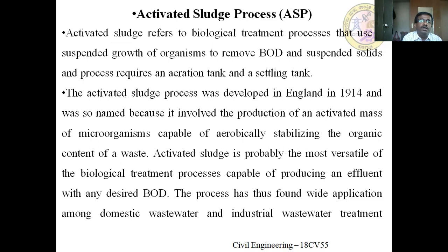Aeration tanks are helpful for mixing the microorganisms with the organic matter and maintaining the system in suspension. For that, in the aeration tank we supply oxygen naturally or artificially. The settling tank is usually termed the secondary clarifier or secondary settling tank, and it is helpful for settling the solids present in the mixture of organics and microbes, and also for separating the wastewater from the activated sludge.